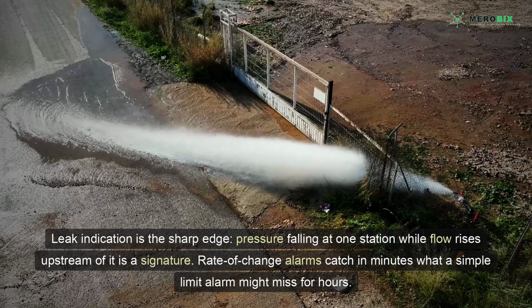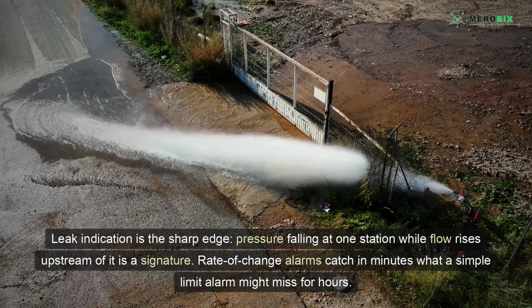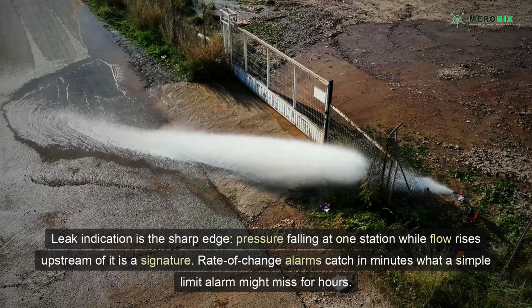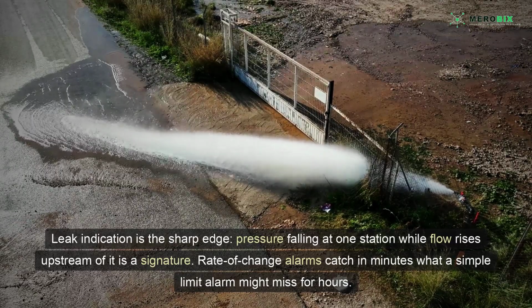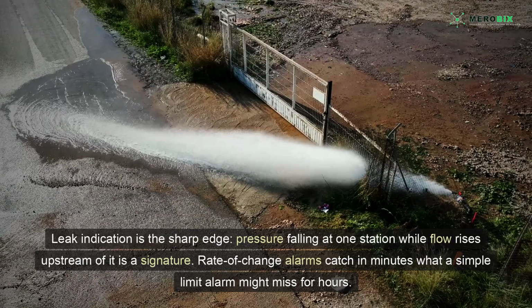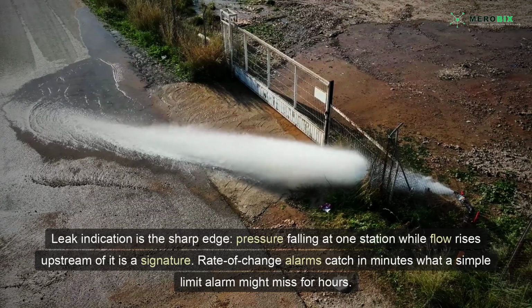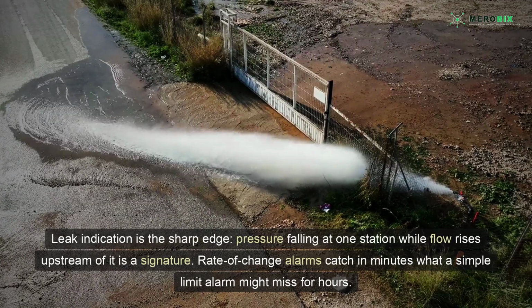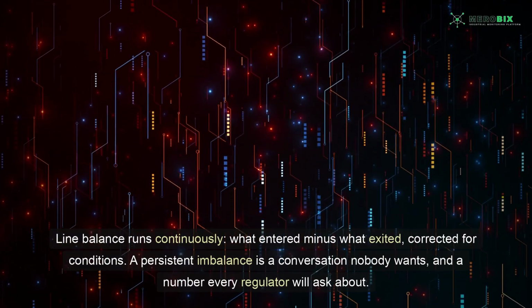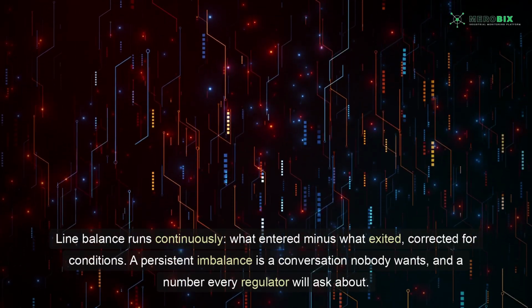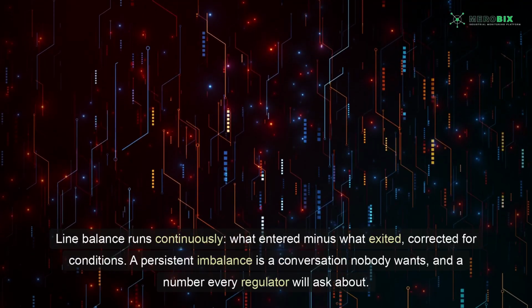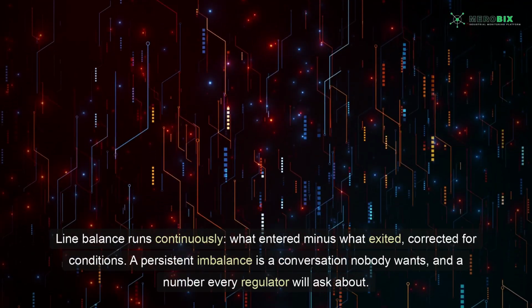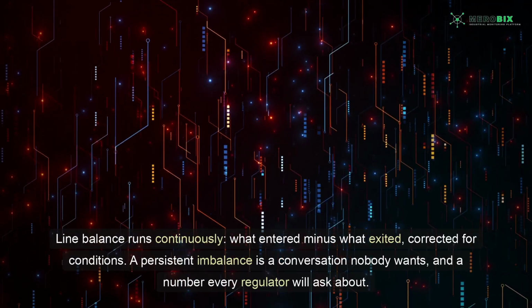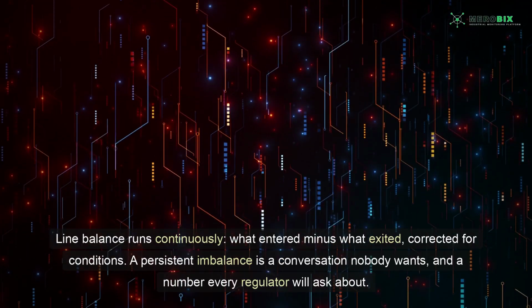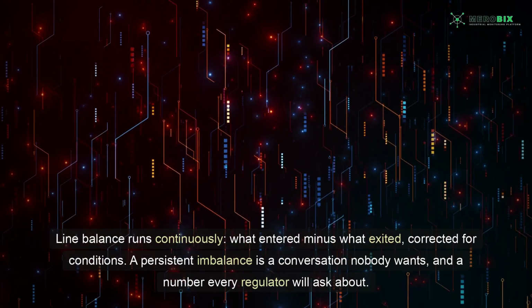Leak indication is the sharp edge. Pressure falling at one station while flow rises upstream of it is a signature. Rate of change alarms catch in minutes what a simple limit alarm might miss for hours. Line balance runs continuously, what entered minus what exited, corrected for conditions. A persistent imbalance is a conversation nobody wants, and a number every regulator will ask about.